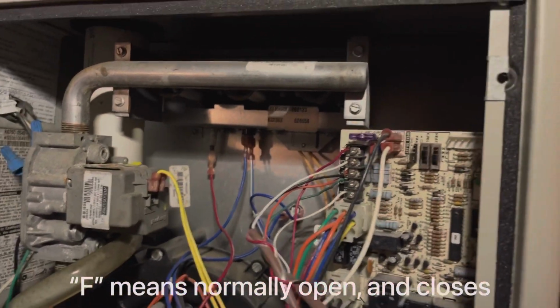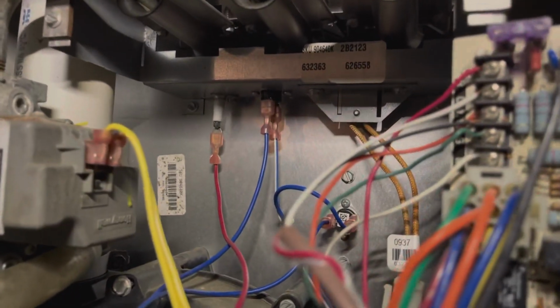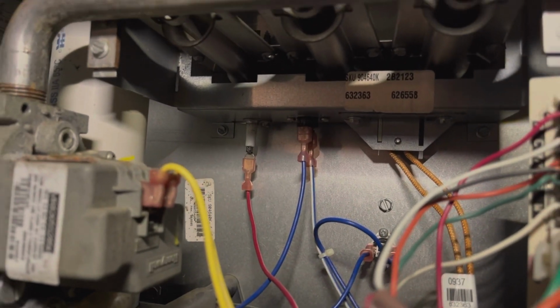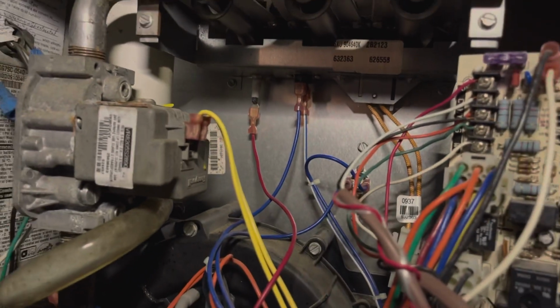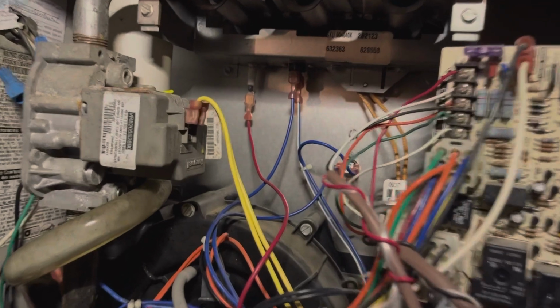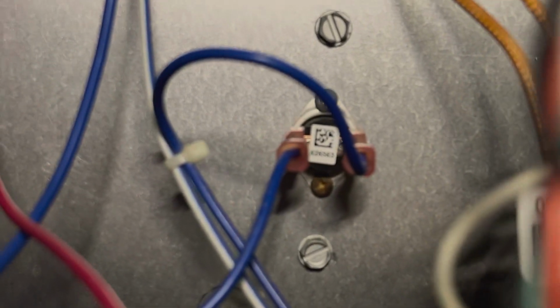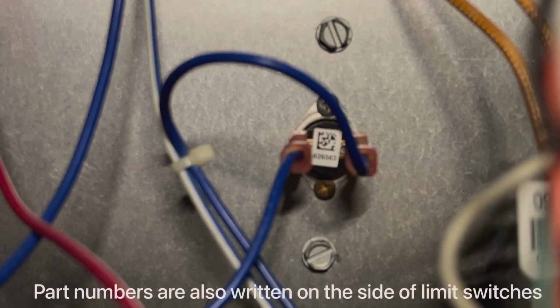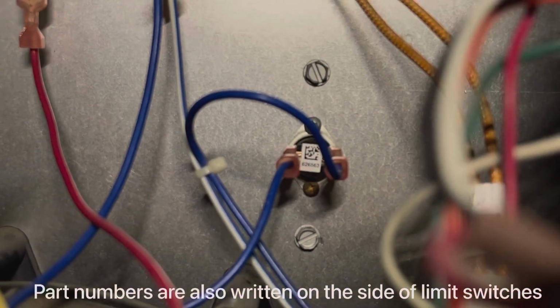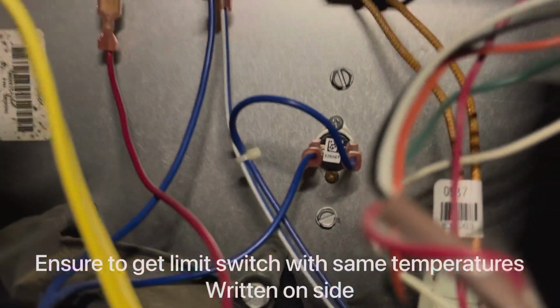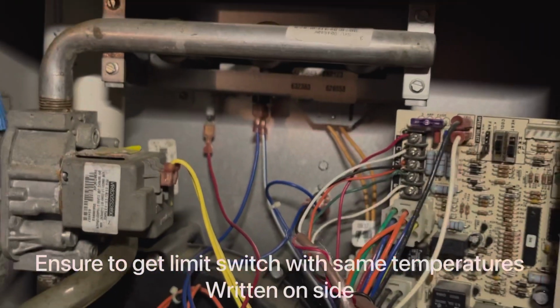And like I mentioned, maybe afterwards I could pull one off and show you, but the temperature is written on the side of when it's supposed to open and close. So you want to make sure you get the right part number. You can see this one here. There's a little QR code, and I think that's the part number, and there's the writing written around on the side of it. Okay, so no more delay. Let's start up this furnace and watch it fire up.